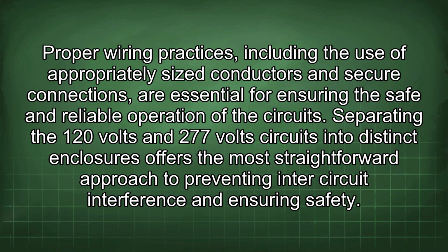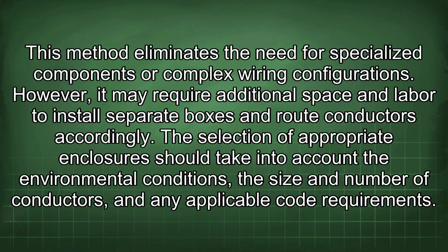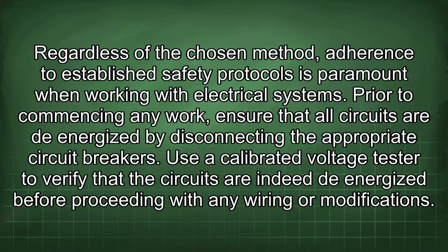Separating the 120 volt and 277 volt circuits into distinct enclosures offers the most straightforward approach to preventing inter-circuit interference and ensuring safety. This method eliminates the need for specialized components or complex wiring configurations. However, it may require additional space and labor to install separate boxes and route conductors accordingly. The selection of appropriate enclosures should take into account the environmental conditions, the size and number of conductors, and any applicable code requirements.